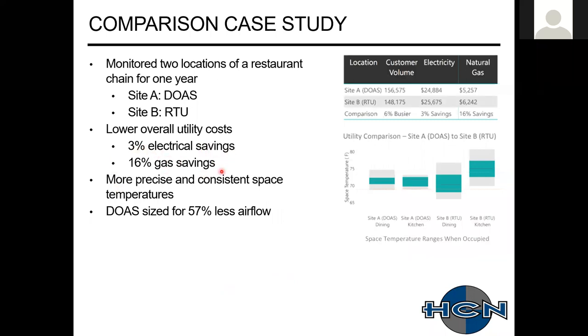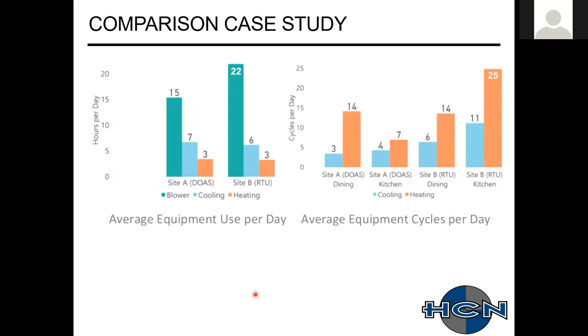They were able to lower the electricals and gas. And then the big thing with that was your precise control. You didn't have as much fluctuation with the systems. Typically with most of the fluctuations on the system with the standard rooftop units, your compressor's turning on and off. So they're cycling. So this went over the different cycles and then the average equipment. So they were able to have a 32% reduction in equipment runtime. So you had less cycling happening. I think it's almost 60% fewer cycles.